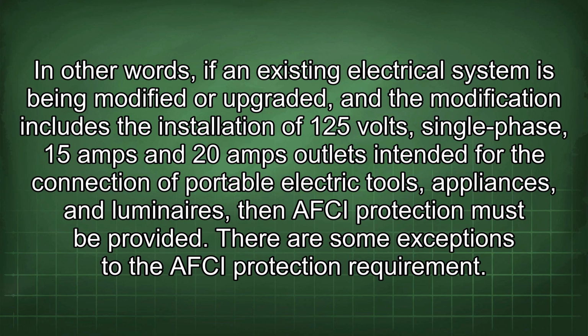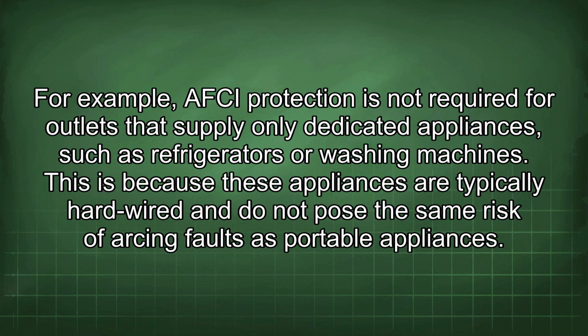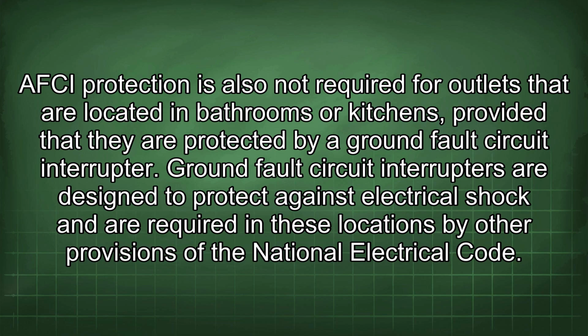There are some exceptions to the AFCI protection requirement. For example, AFCI protection is not required for outlets that supply only dedicated appliances, such as refrigerators or washing machines. This is because these appliances are typically hardwired and do not pose the same risk of arcing faults as portable appliances. AFCI protection is also not required for outlets that are located in bathrooms or kitchens, provided that they are protected by a ground fault circuit interrupter. Ground fault circuit interrupters are designed to protect against electrical shock and are required in these locations by other provisions of the National Electrical Code.